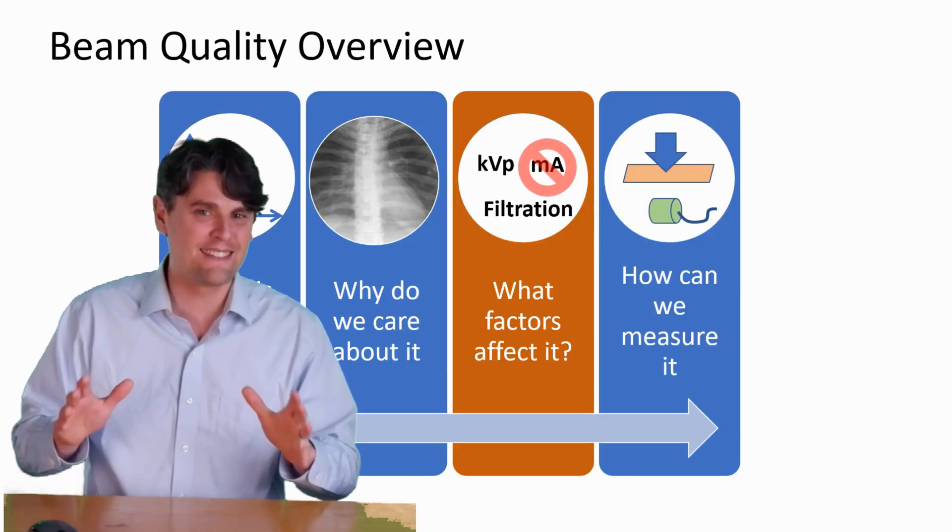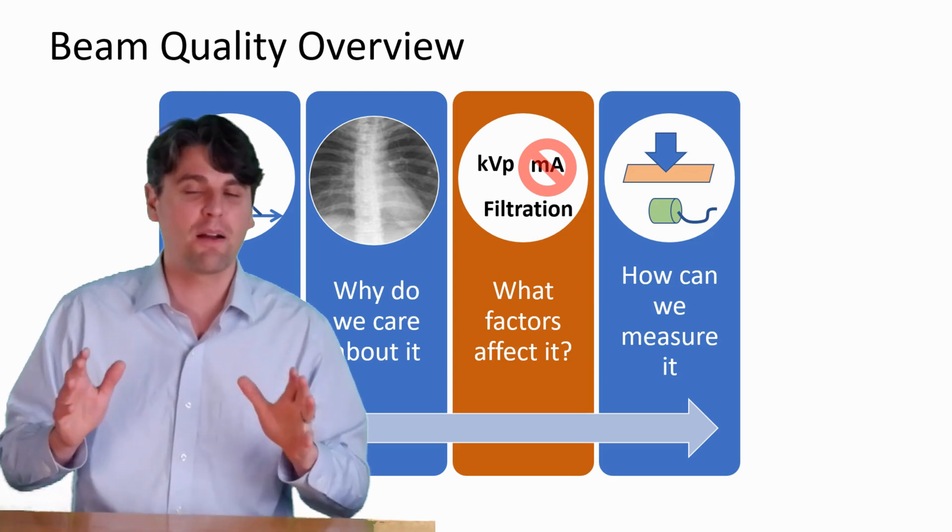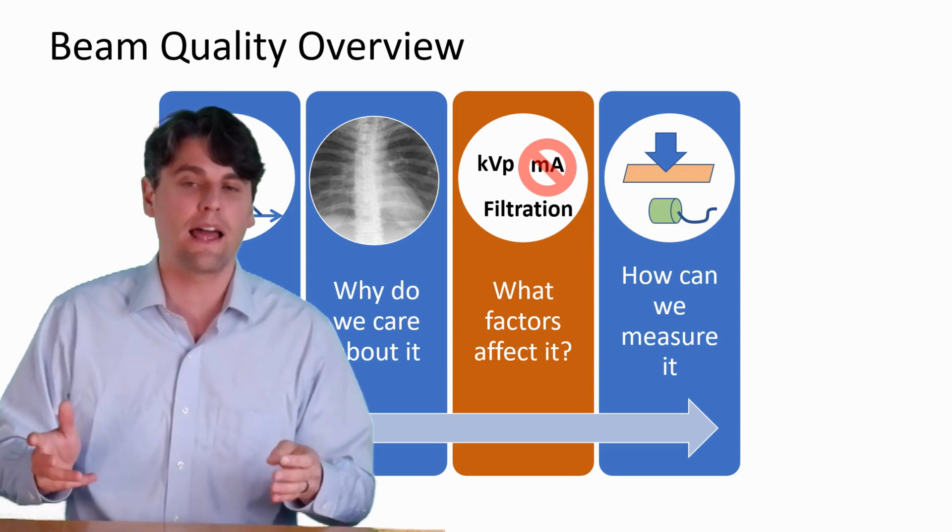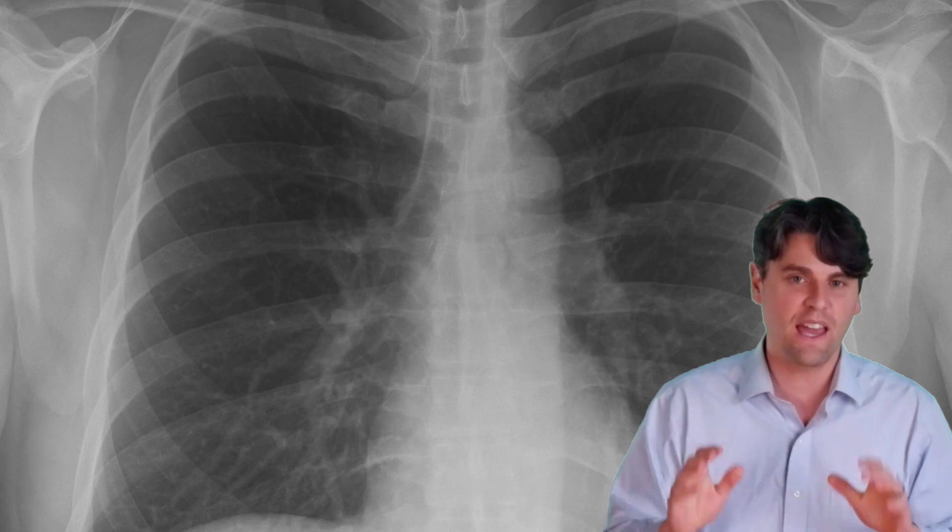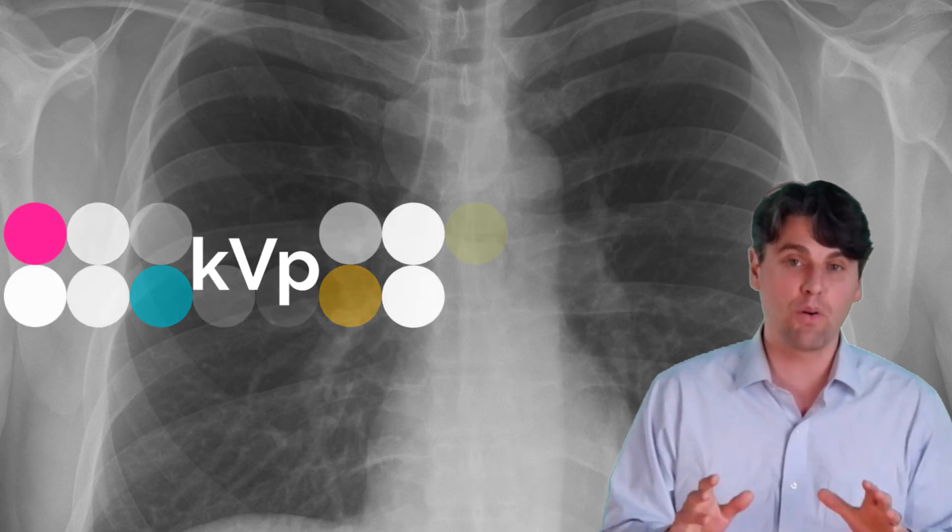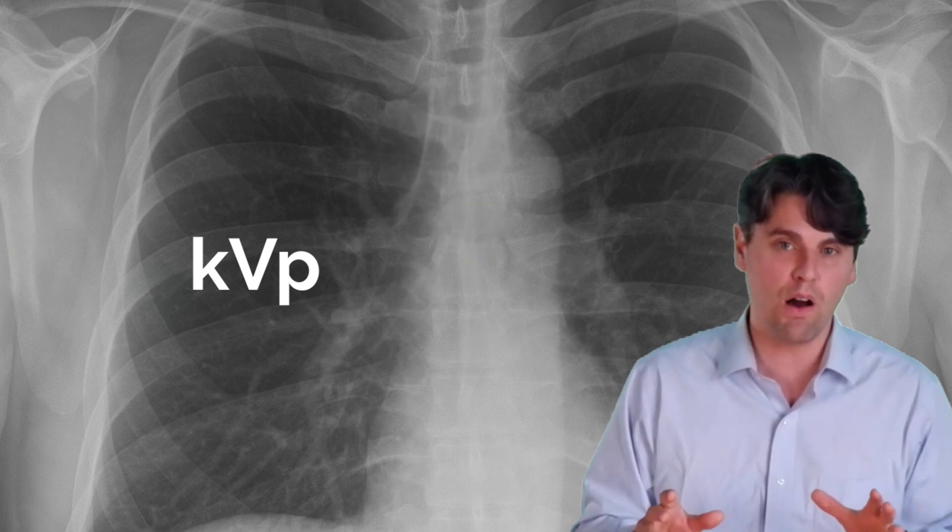Do you know what beam quality is now? We know we definitely care about it a lot, right? And we care about it because it changes the image quality a lot. We'll talk about what factors actually influence the beam quality. First off, KVP. This is the factor that you're mostly going to be changing on your system in order to influence the beam quality.